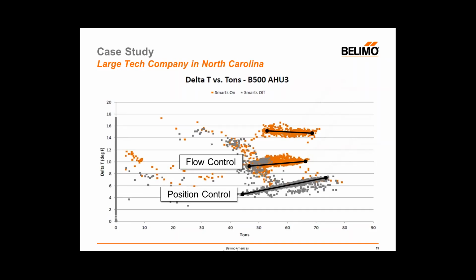And so now they have a similar load range. It's a couple of weeks later, so the loading's not exactly the same, but we're still in that mid 40s to, in this case, high 60s tons range. And they're doing it on average at about 10 degrees delta T. So if they were averaging 6 before, now they're around 10, which is a sizable improvement.